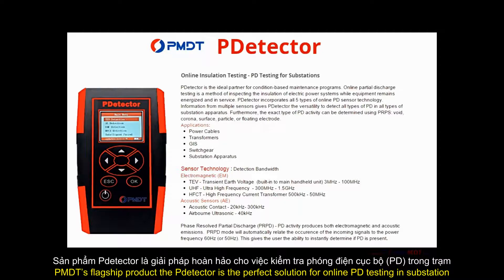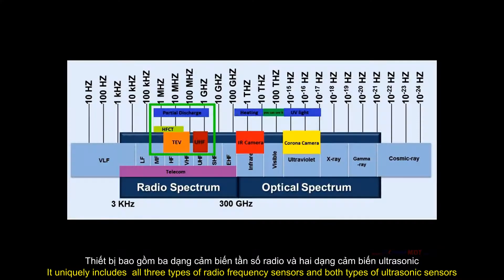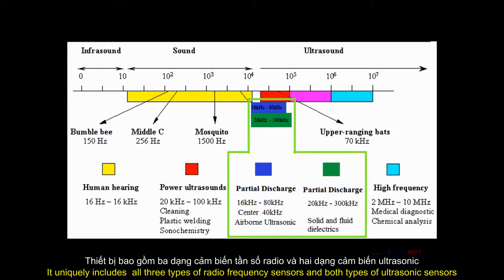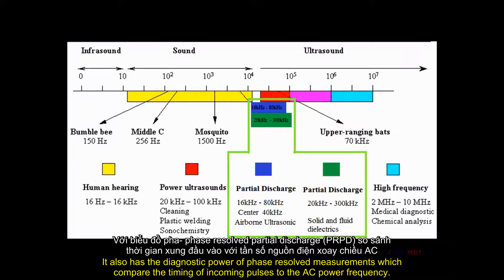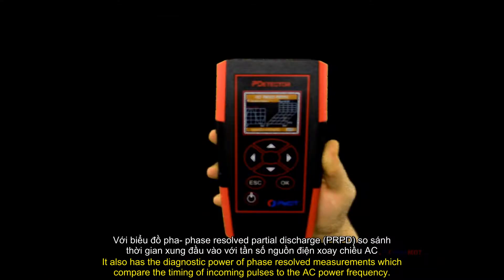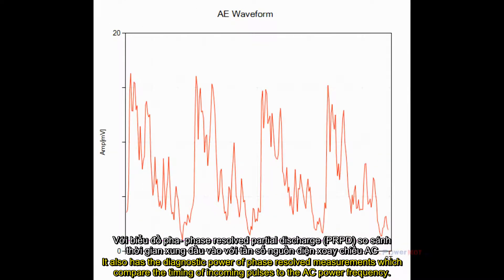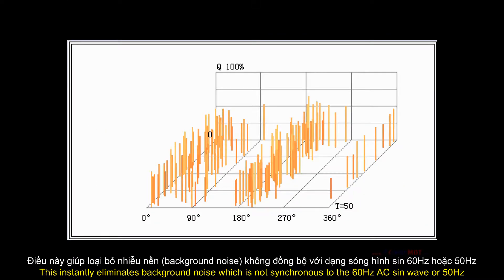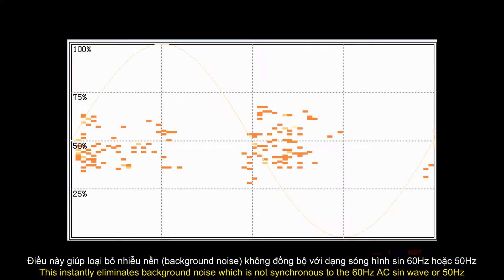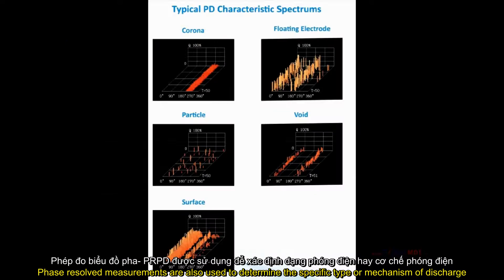PMDT's flagship product, the PDtector, is the perfect solution for online PD testing in substations. It uniquely includes all three types of radio frequency sensors and both types of ultrasonic sensors. It also has the diagnostic power of phase-resolved measurements, which compare the timing of incoming pulses to the AC power frequency — instantly eliminating background noise not synchronous to the 60 Hz AC sine wave. Phase-resolved measurements are also used to determine the specific type or mechanism of discharge.